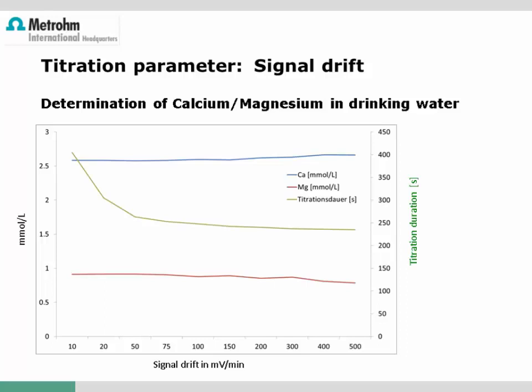A practical graph shows the titration of calcium and magnesium in drinking water using signal drift criteria up to 500 mV/min. Up to 50 mV/min, there is a major impact on titration duration without affecting precision. At higher values, the titration does not get significantly faster but results start becoming less precise.